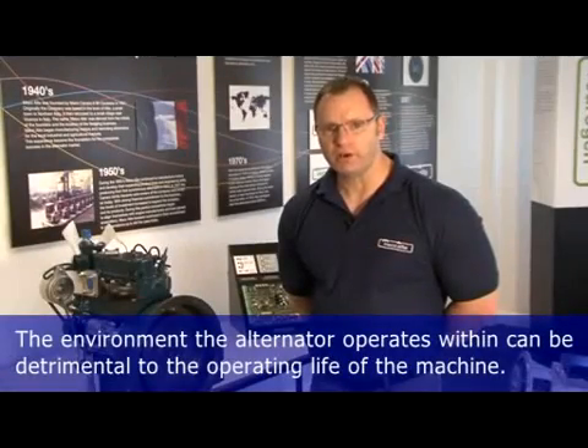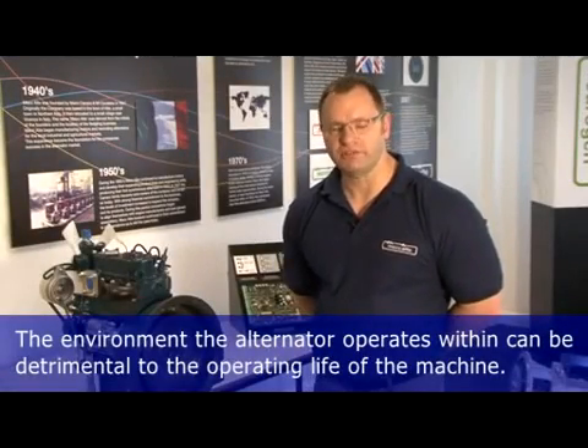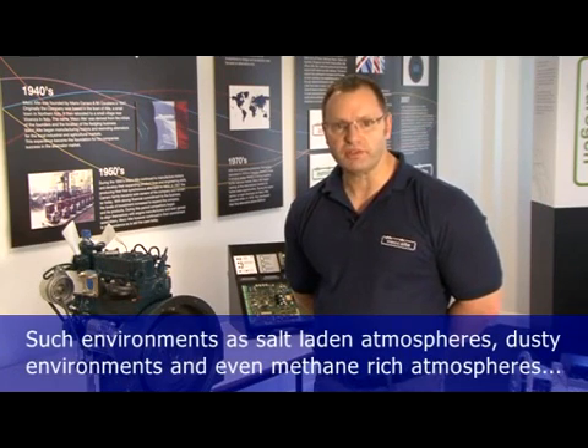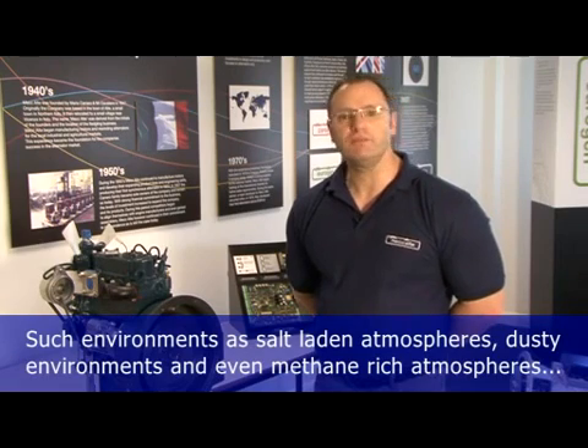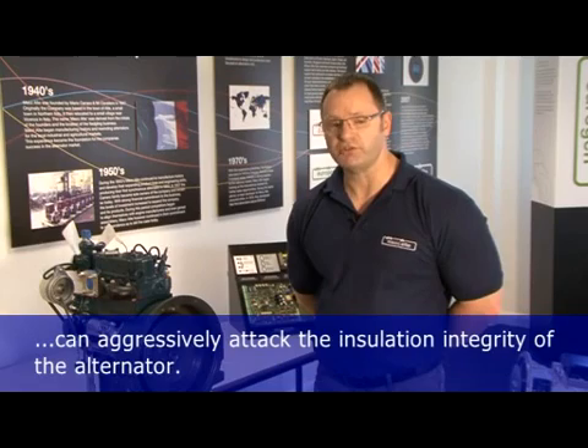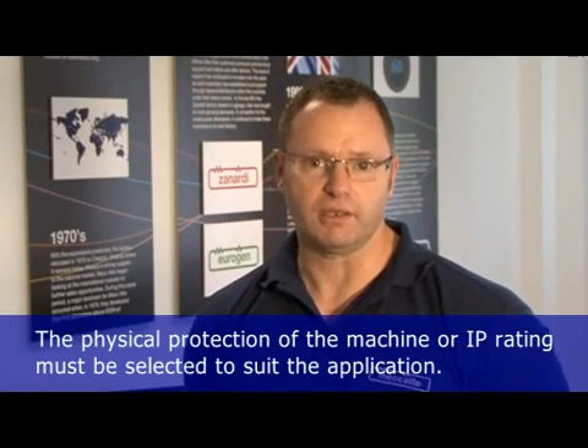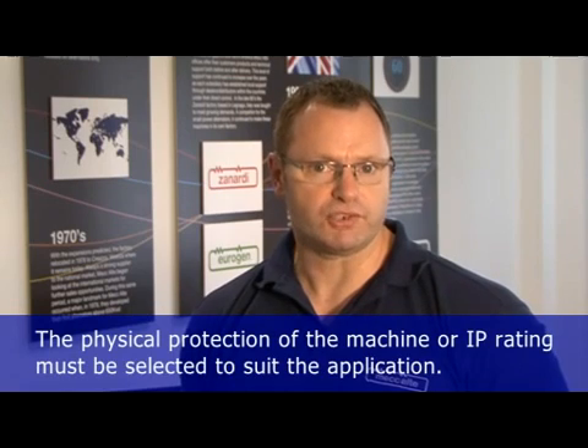The environment the alternator operates within can have a detrimental effect on the life of the alternator. In this video, we look at the optional insulation systems available for the Macalty alternators. Such environments as salt-laden atmospheres, dusty environments, even methane-rich atmospheres can aggressively attack the insulation integrity of the machine. The physical protection of the machine, or IP rating, must be selected to suit the application.